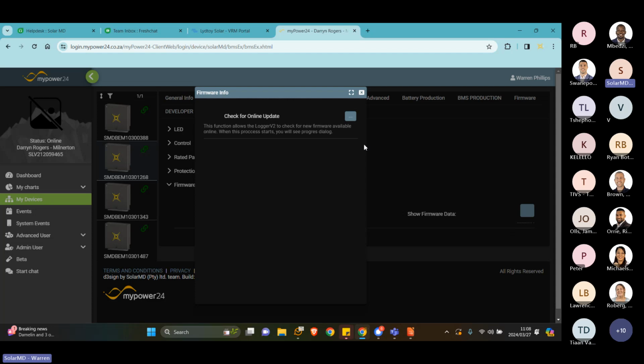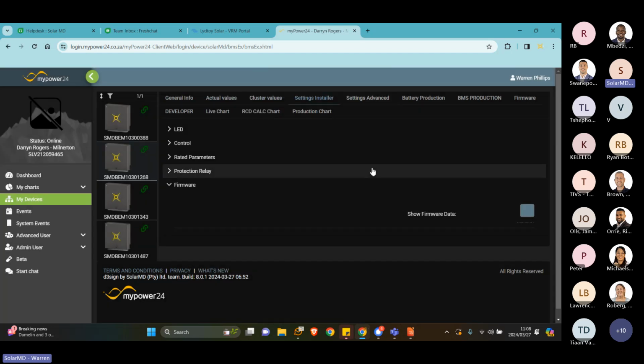You would download it. It's a small file. It's only a few hundred kilobytes. And then you would upload it to the battery, and you would choose the install option. That would then install the firmware onto the BMS. The BMS would turn off and on, because it's essentially like formatting a computer. It's going to have to shut down and reboot. So keep that in mind.